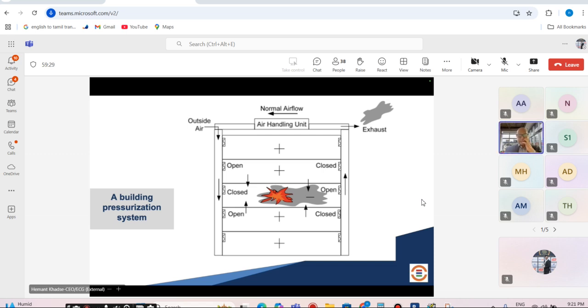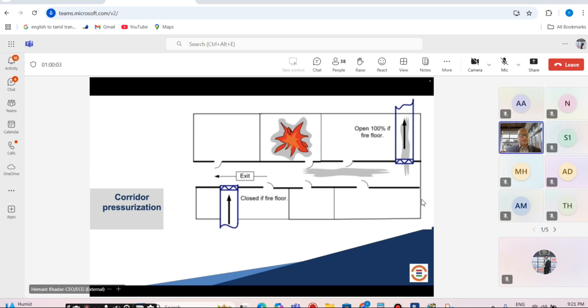So this is again the example that I want to illustrate here, just to explain the principle of smoke management, especially in a high-rise building, how you are going to create your smoke zone activated with exhaust, and adjoining floors, which are above and below, creating positive pressurization so that the smoke doesn't transfer to the upper lobbies, upper floors. So this is the job of a life safety engineer, to ensure that the system is reflected as part of your cause and effect diagram.